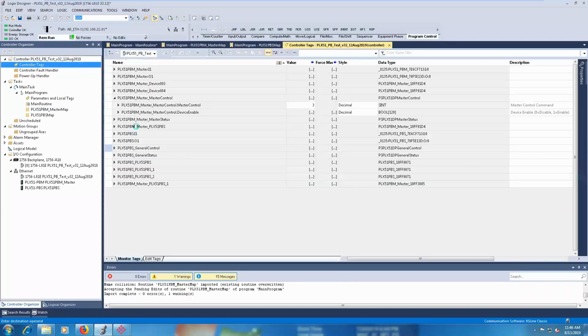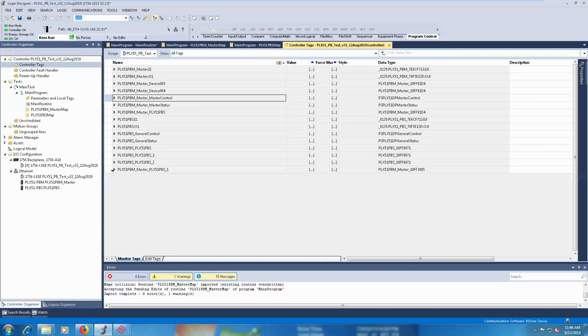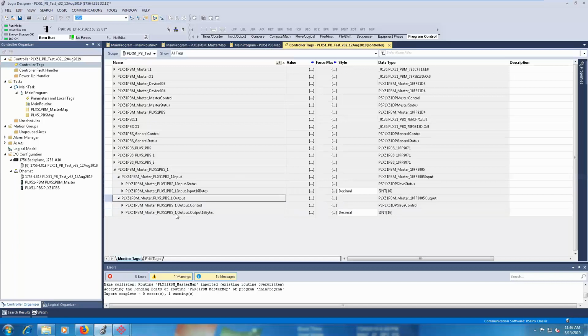And then now we've got some controller tags in here that got automatically mapped in for us. In this instance, we'll have the input and output data directly into the processor. It creates that tag and those 16 bytes of information that we're getting from that device right there. So as you can see, the Logix integration, or Studio 5000 integration, does provide some great benefits that should help speed up commissioning time.